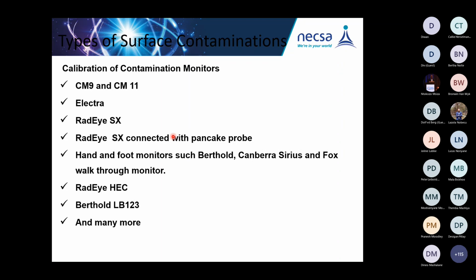On that note, an instrument is calibrated with its probe. If you have 2 or 3 instruments which are similar, and one instrument becomes malfunctioning, you cannot swap the probe. It is strictly prohibited. The settings for that instrument were meant for that specific probe which was calibrated with it. In most cases, people say that because the other probe was calibrated, therefore we can swap. No, you cannot swap because the settings won't be the same. Rather send it back to the calibration laboratory, and they will calibrate the working probe in case another probe or the instrument is damaged.